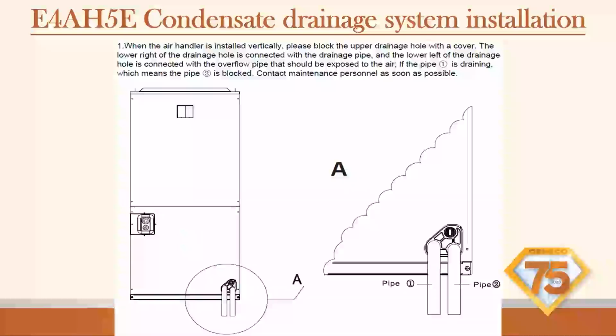When the air handler is installed vertical, please block the upper drainage hole with the cover. I know in some jurisdictions, they do have you pipe out both. So here's our primary. If the primary plugs, our secondary is going to drain possibly into the drain pan, which if you have a drain pan with a wet switch, is going to trip the wet switch, right? So I know in a lot of jurisdictions, they are making us pipe out both. The primary goes to the outside, secondary goes into a drain pan or some kind of wet switch.